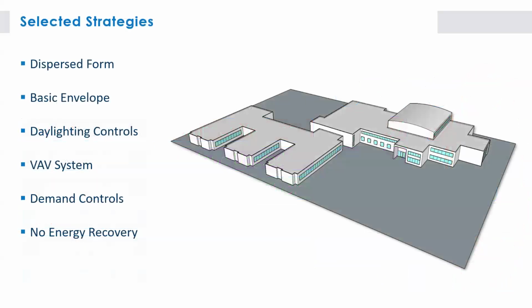So they went with a disperse form, basic envelope, daylighting controls, VAV system, demand controls, and opted against the energy recovery system. The reason they did that: they were worried about the maintenance concerns from the energy recovery system. So they opted against it.